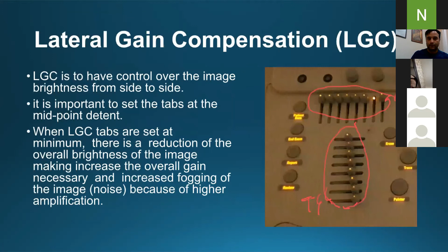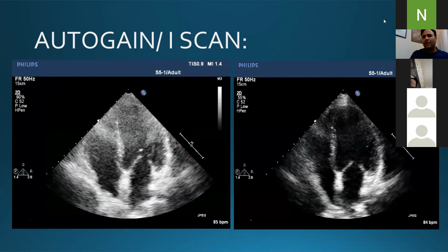I know it is a bit dry. See, this is the picture. When you put this apical 4-chamber view, you have made this view without fiddling with any of the knobs. Now, when you press iScan, this button, automatically it selects. See, the gain is 55, compression is 52. Here gain is 90%. So automatic scan, or this auto gain or iScan, automatically selects the appropriate parameters for the image. This is widely available in newer machines. You don't have to worry about that. Depth.